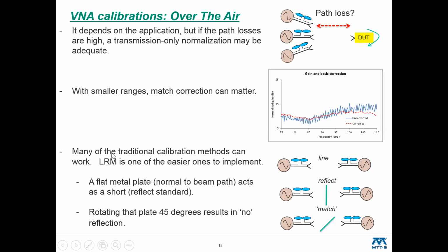And many of the calibration methods in the alphabet soup we looked at earlier will all work when you do have to think about match. But one method is reasonably popular in that space. That's the Line, Reflect, Match algorithm. And it's a little counterintuitive at first how these standards are arrived at. But if you think about it, a line, that's sort of easy. You're pointing your 2 antennas at each other. A reflect could be a short, that's just a metal plate normal to the path.